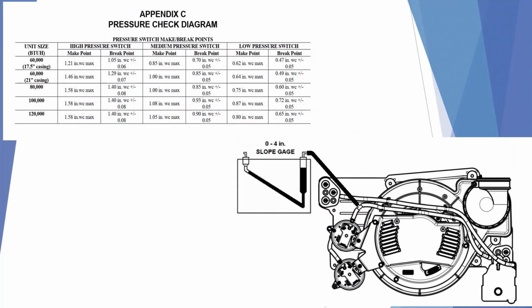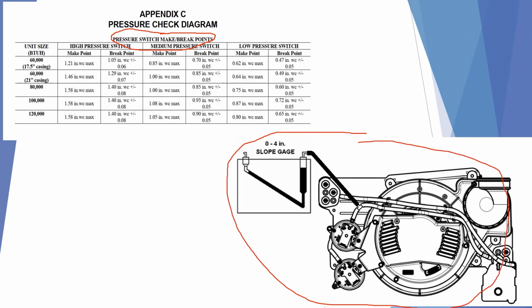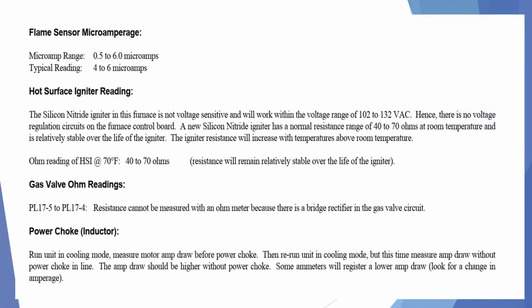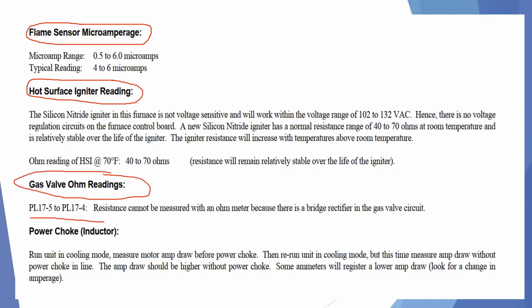Now, normally in the appendix of the troubleshooting guides, you will find things like this, like your pressure switch make and break points, which is very important information for you to troubleshoot a furnace. They'll also give you diagrams of how you should set up your slope gauge or Magnehelic or whatever gauge you're using to read these things. And then you'll also have information like your microamperage on your flame sensors, what you should be reading there, ohm readings on your hot surface igniters, gas valve ohm readings, and possibly, if your furnace has it, a power choke inductor. So you'll find all kinds of good information in these troubleshooting guides to help you troubleshoot properly.